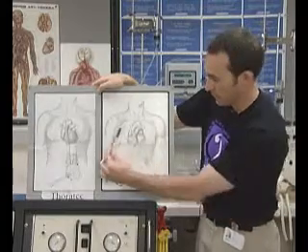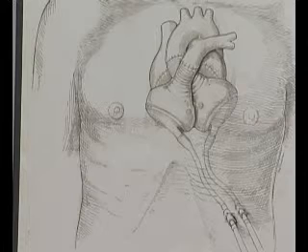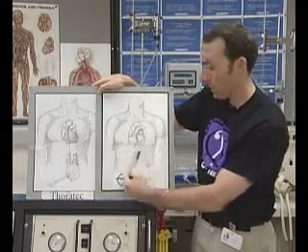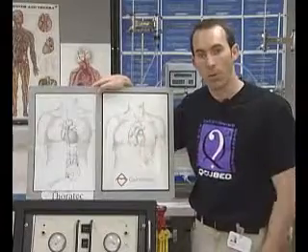And you can see how it's connected. The right side would come in. Just as we were talking about, blood flow would come into the device. There would then be a pneumatic, or air pressure, that would provide the pressure needed to overcome the pressure of the lungs and the body to keep that circuit going.